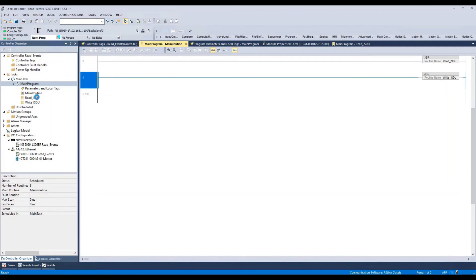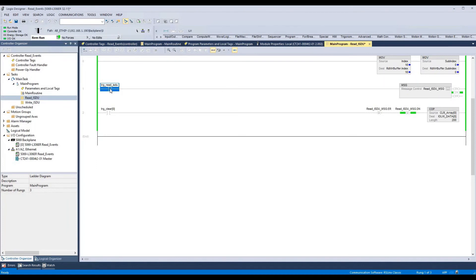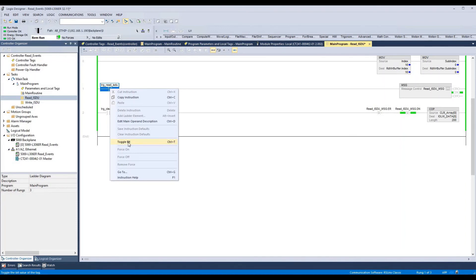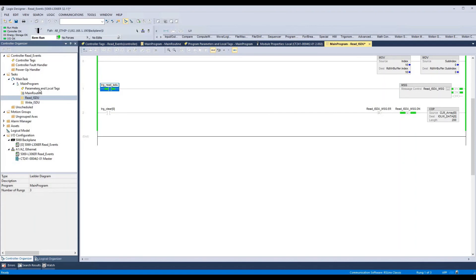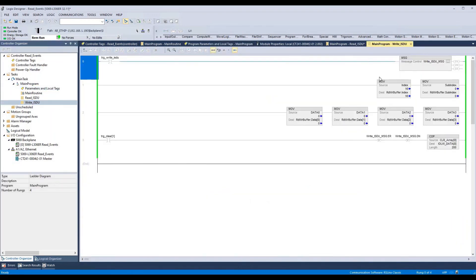We can go to the ReadISDU routine and set the source to index 16 and subindex 0 for reading the vendor ID. Now we will trigger the ReadISDU bit by right-clicking and selecting Toggle bit. We can go to the parameters and local tags, and we can see that we have read 'Balluff GmbH', which is the vendor ID of this device. The same can be done for the WriteISDU by setting the index and subindex and triggering the WriteISDU.